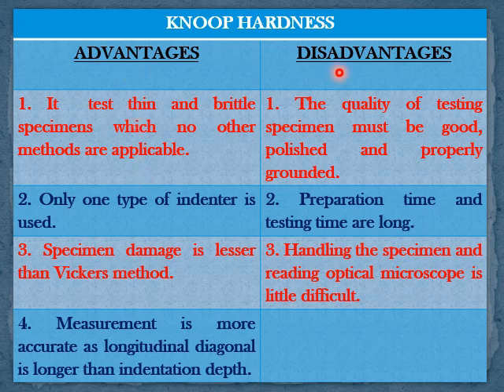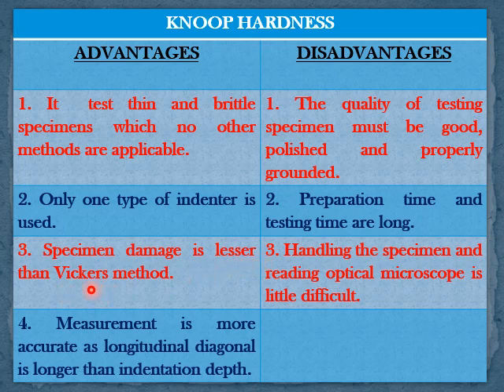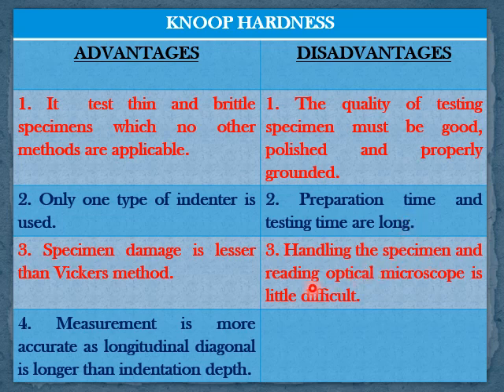Advantages and disadvantages of Knoop hardness testing. Under advantages: the method is applicable to test thin and brittle samples where no other methods are applicable; only one type of indenter is used; specimen damage is lesser compared to the Vickers method; and the measurement is more accurate as the longitudinal diagonal is longer than the indentation depth. Under disadvantages: the quality of the testing specimen must be good — polished and properly ground; both preparation time and testing time are long, making it a time-consuming method; and handling the specimen and reading the optical microscope is more difficult compared to the Vickers method.